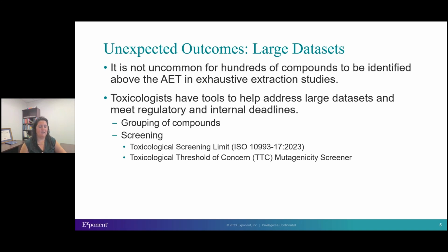So for long-term permanent implants, in order to protect against carcinogenicity, that TTC threshold is 1.5 micrograms per day. But for the compounds we demonstrate to be non-genotoxic, we can then rely on 90 micrograms per day.